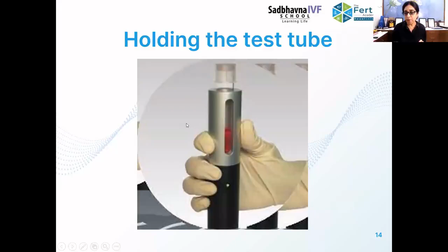But even if everything is calibrated at 37 degrees centigrade, the ovum pickup needle also needs to be preheated in a dry incubator, or you can keep it on the lab guard table. But even if everything is preheated, it has been seen, in a very nice experiment, that there was a drop of temperature of 7 degrees. They had kept thermocouples at different points, and the maximum drop was from this point to this point. That is, the fall was not in the ovum pickup needle, but when it came from the ovum pickup needle to the test tube. So this drop of 7 degrees was there.